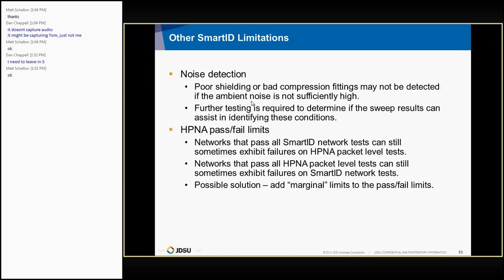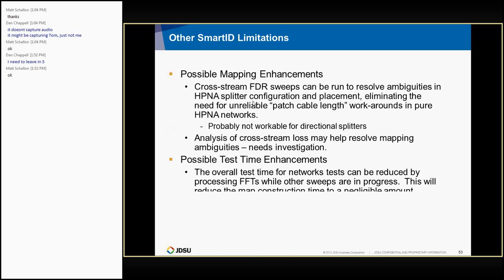Noise detection is another limitation in the sense that it relies on an absolute noise measurement. If you don't have enough ambient noise at the time of taking the measurement, you may not detect that you have poor shielding. Also, on the HPNA pass-fail limits, in actual testing, what we observed is that when you get close to the edge, you can have Smart ID networks that pass the Smart ID test but still have HPNA packet-level test failures, and vice versa. We don't have right now a marginal, yellow warning region where we indicate that you're close to the edge. So that's why we get these kinds of conditions.